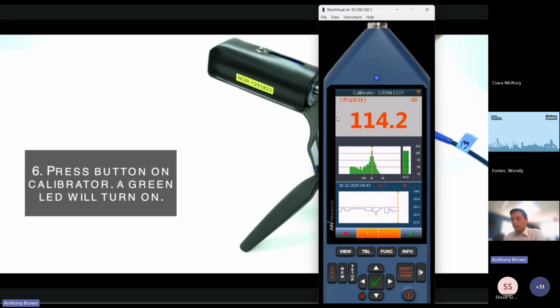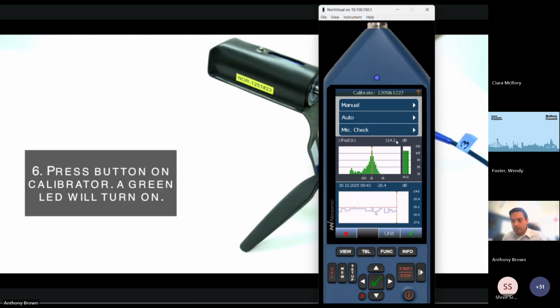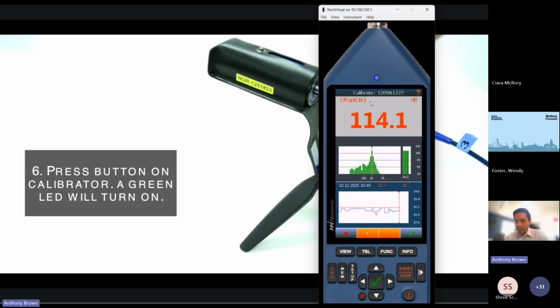It should look like this. Or if you're in just this screen here, it will show you the number in very small letters here, 114. You're looking to match what's on the calibrator. Some people can just press auto and then press calibrate, and it will adjust the level itself until it reads 114. Then it'll flash up finished, and you just press a tick to save it. Or if you want to do it the manual way, you just press the minus or plus button at the bottom until it reads 114.